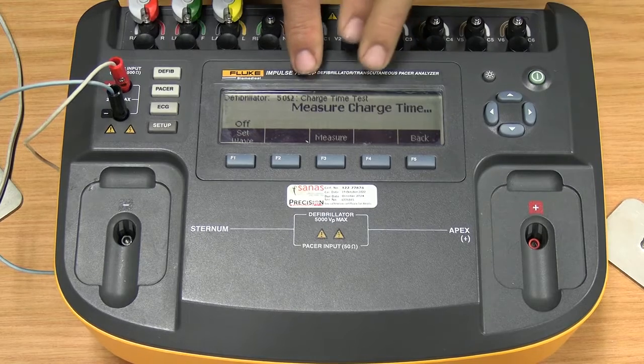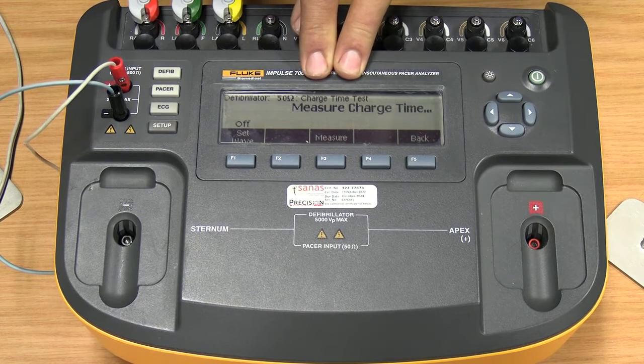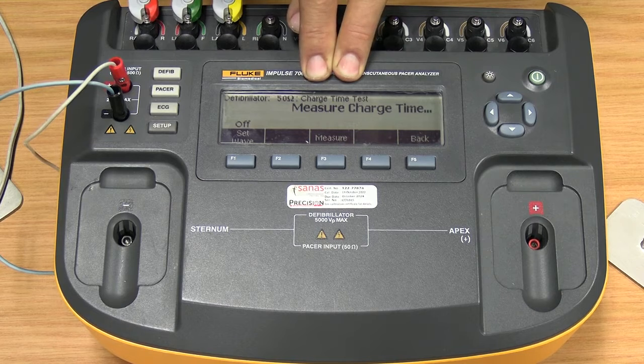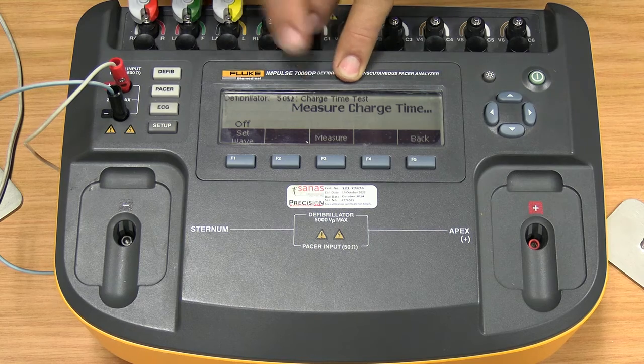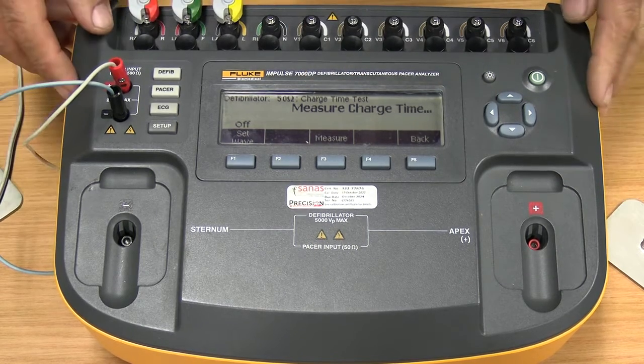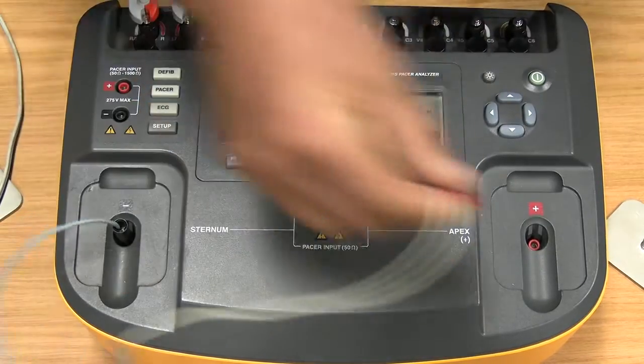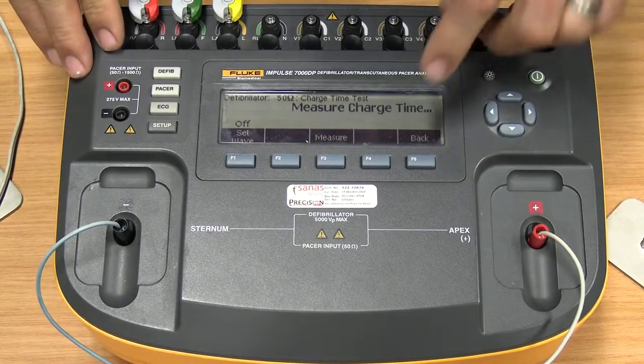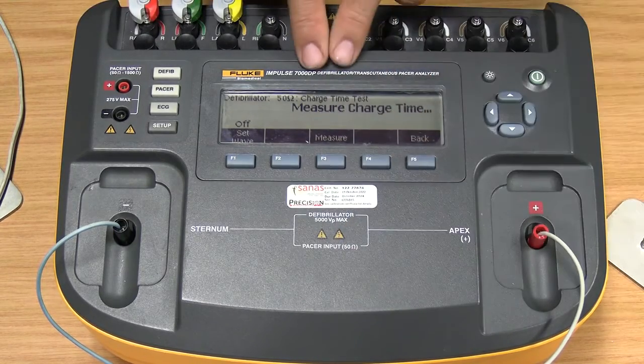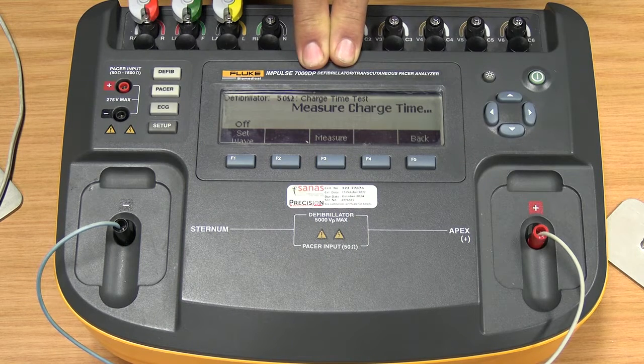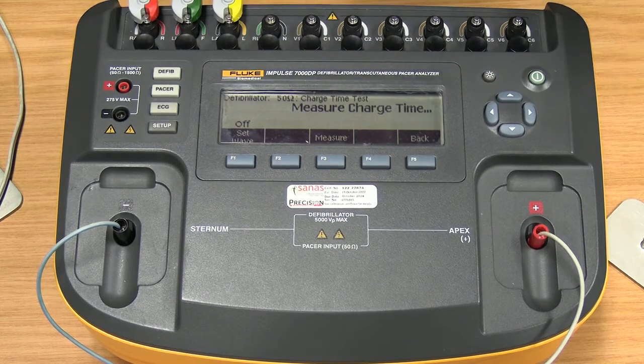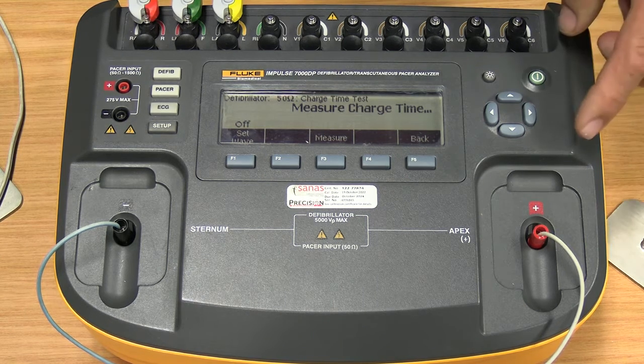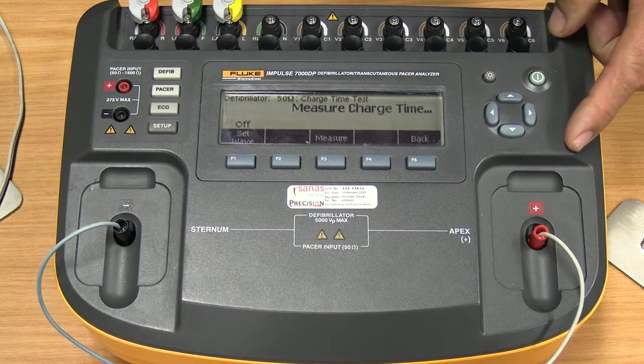All we want to do here is measure how long it takes the defibrillator, after you've pressed the charge button, to reach its maximum energy level. So what you need to do is set your defibrillator at the required energy level, apply your paddles or your internal electrodes, as we've done here. And then the moment you press the measure button, it's going to give you a few seconds countdown. And once it reaches 0, you need to press charge on your defib. And the moment you reach energy, you need to press shock. And that time from the moment you press charge to the time you apply the shock, that is your charge time, which will be measured by the unit.